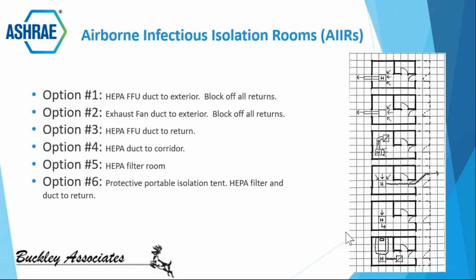The last option though, number 6, is basically utilizing some sort of protective portable isolation tents. We're seeing these tents being used in those larger open facilities to create individual isolated areas for these patients. In this case, the air is going to be pulled out of this tent, HEPA filtered, and then exhausted either out of the building or into the return of an existing room. There are obviously more options than this. These are the specific 6 options that ASHRAE presented in the last 2 weeks.